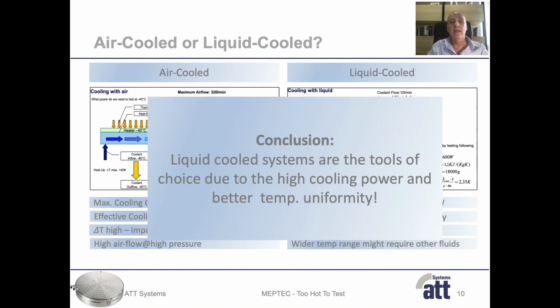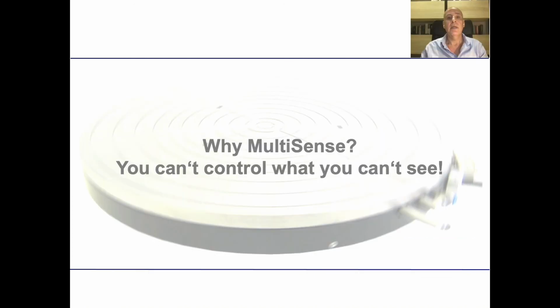Okay, let's summarize. Liquid-cooled systems provide significantly larger cooling capacity. The temperature difference between chuck and coolant is notably lower, which means better temperature uniformities. And these are the reasons why we choose liquid-cooled systems for high power applications. Now we understand that we need to use liquid-cooled systems. But what is multisense and why do we need it?